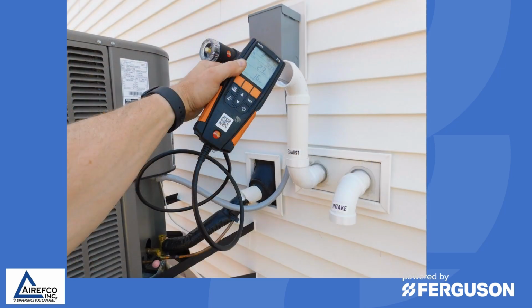Taking a furnace apart to take a look at the secondary heat exchanger is a very labor-intensive endeavor. Before you start tearing the furnace apart, you want to make sure that it is something that needs to be done. By taking a CO reading in parts per million on the exhaust of the furnace, you can tell whether you need to open the furnace up or not.